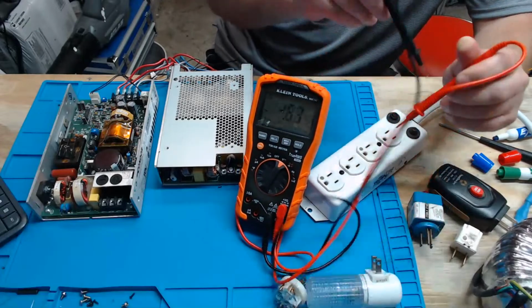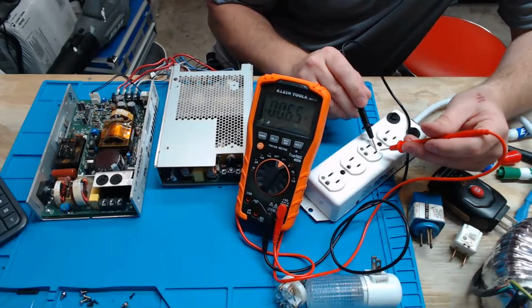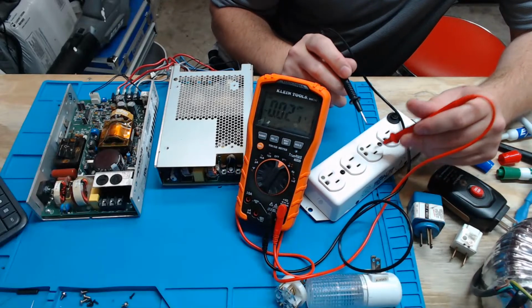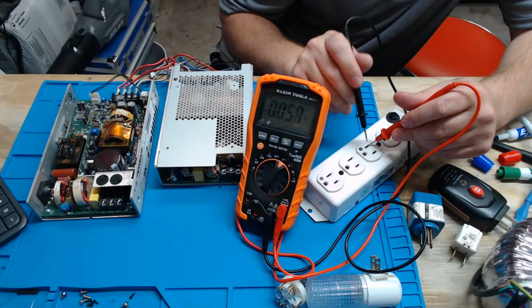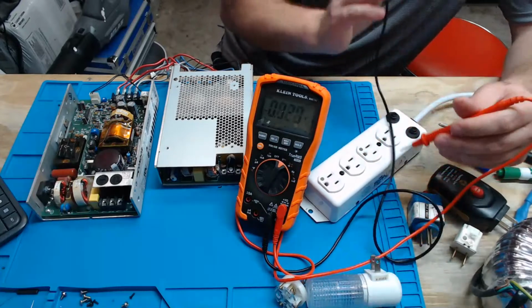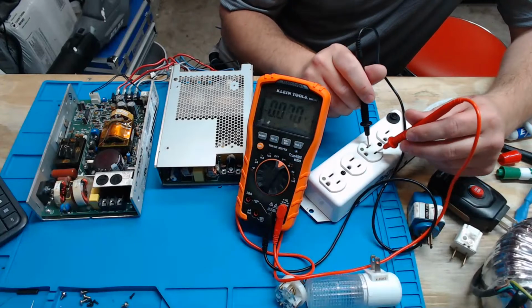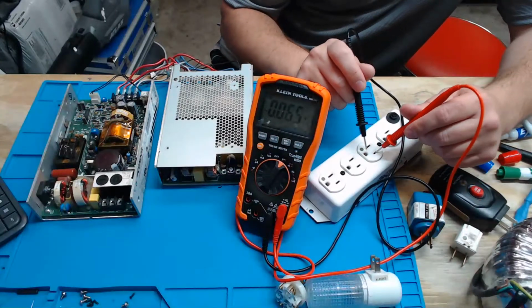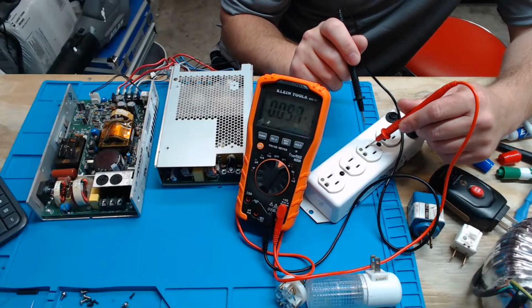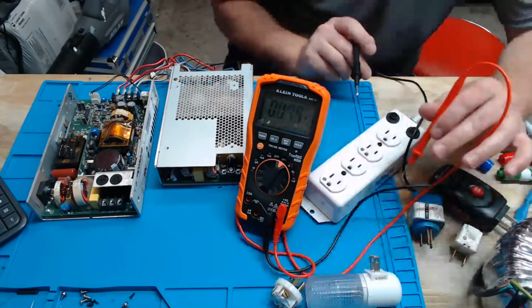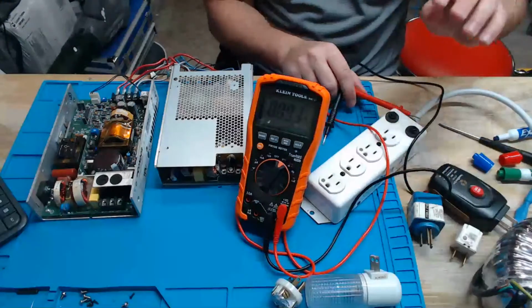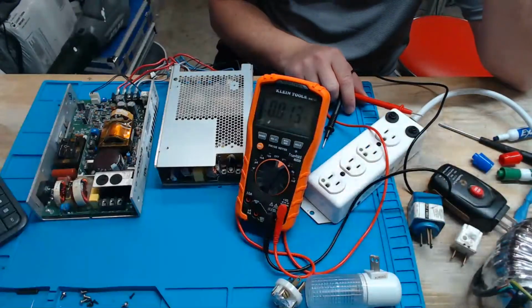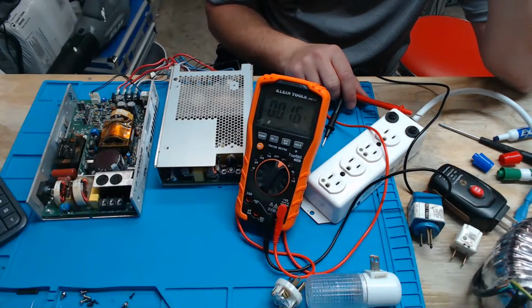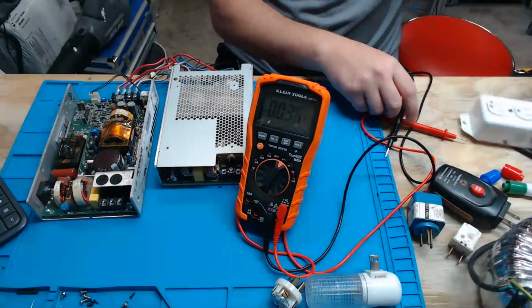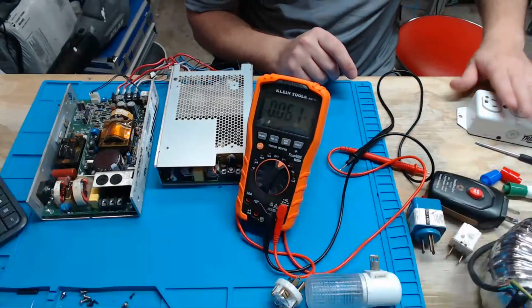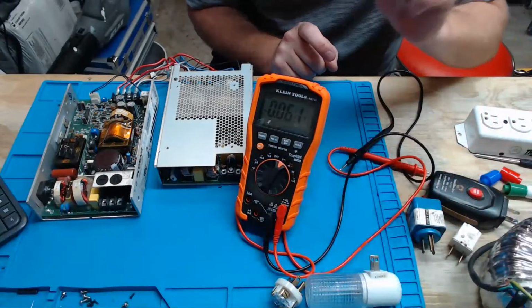So what's going on? Well, in a traditional outlet, from one prong to ground, from line to ground, I will have 120 volts. And from neutral to ground, I will have 0 volts. On this one here, on isolated power, between the two prongs, I have 120 volts potential. But between this prong and ground, or this prong and ground, I should have about 60 volts. Why is that important? Well, I've got a whole video set aside on isolated power. So I'm not going to cover isolated power in this one, but I do want to show you that there is voltage on both line and neutral.